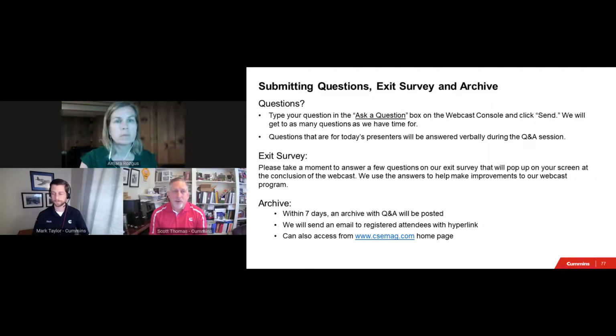This is another question we're getting more recently in the field. I think Mark did a good job of covering this in the presentation as well. When you look at it from a Cummins perspective, most of our diesel engines can run up to a 10 to 20% blend of biodiesel and traditional diesel.